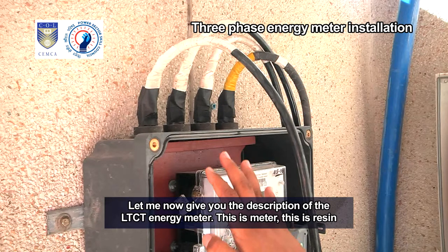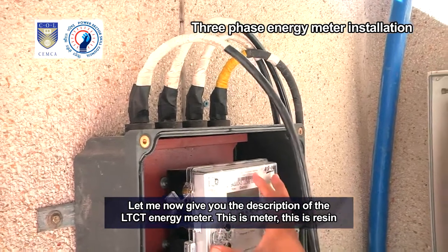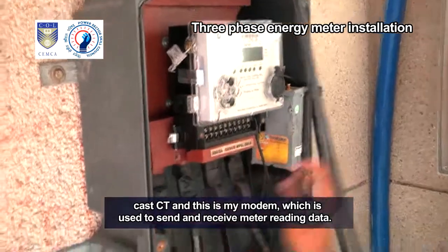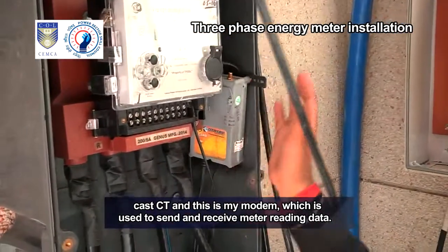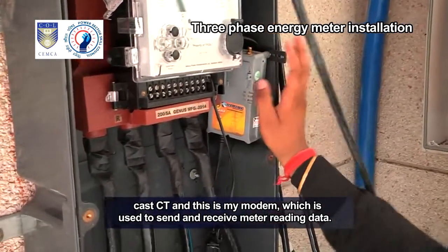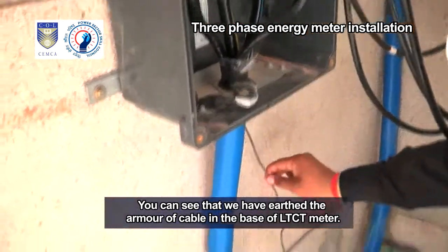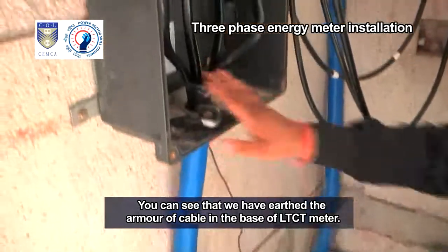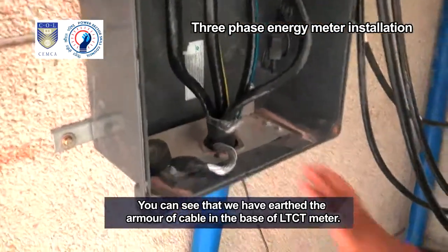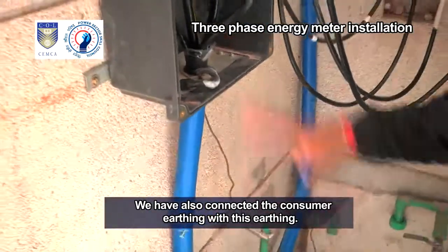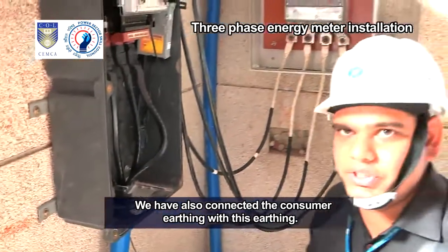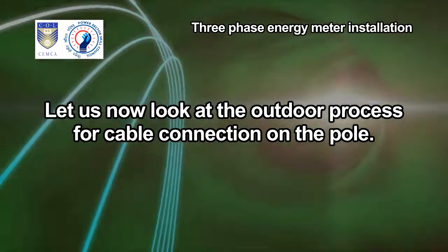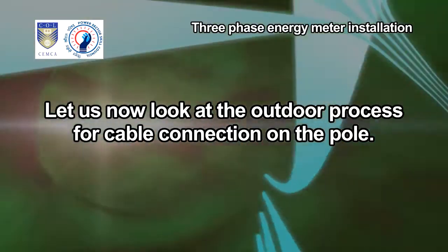Let me now give you the description of LTCT energy meter. This is meter, this is resin cast CT, and this is my modem, which is used to send and receive meter reading data. You can see that we have earthed the armor of cable in the base of LTCT meter. We have also connected the consumer earthing with this earthing. Let us now look at the outdoor process for cable connection on the pole.